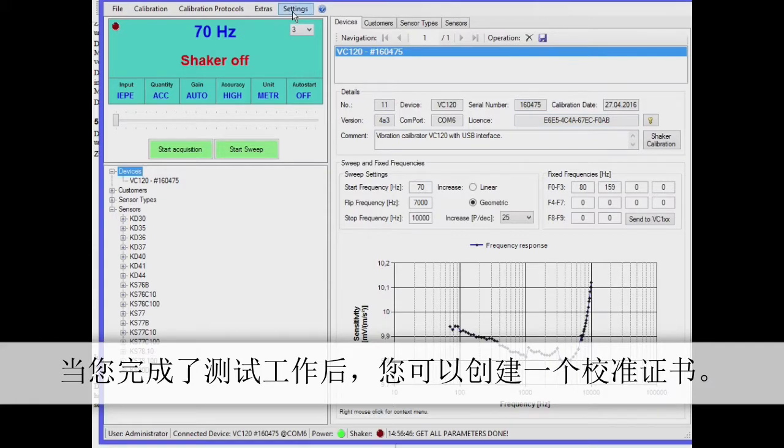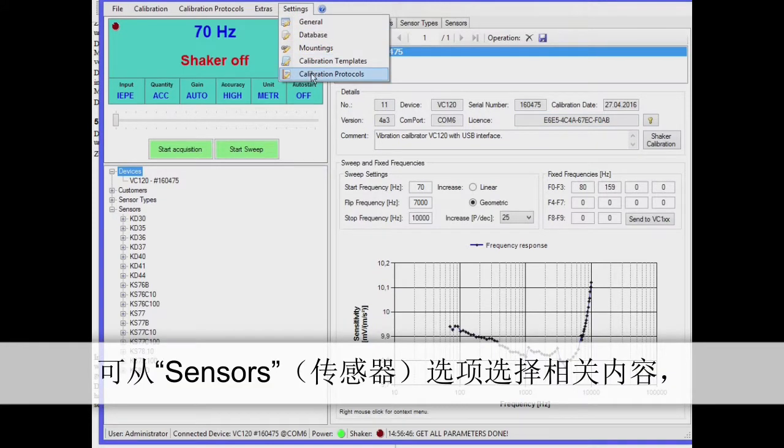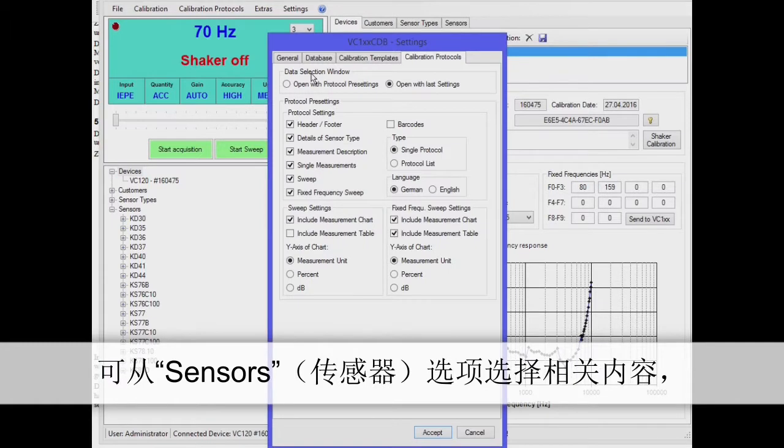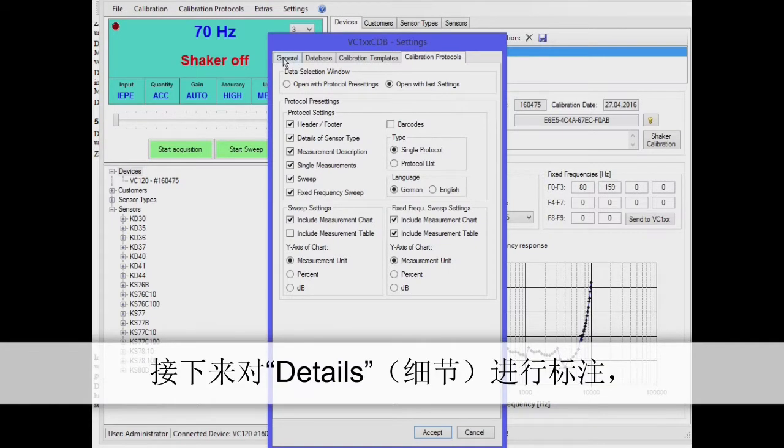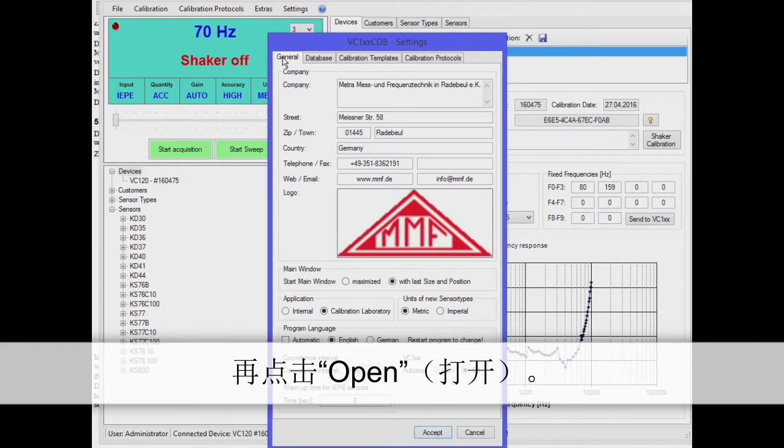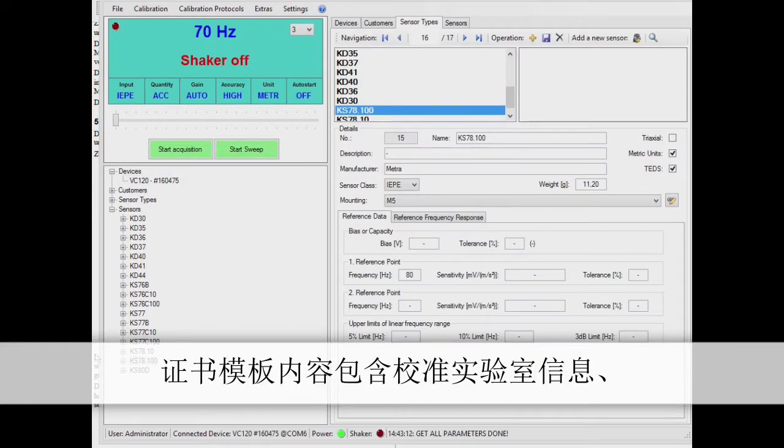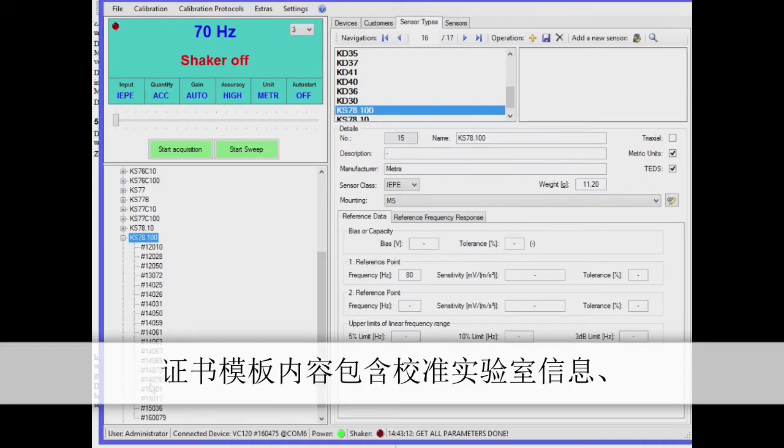When you have finished your measurements you can create a calibration certificate. Select the relevant entry from Sensors, then the tab Details and click on Open. The protocol contains details of the calibration lab, a company logo, the measured values including frequency response and selected typical coefficients.